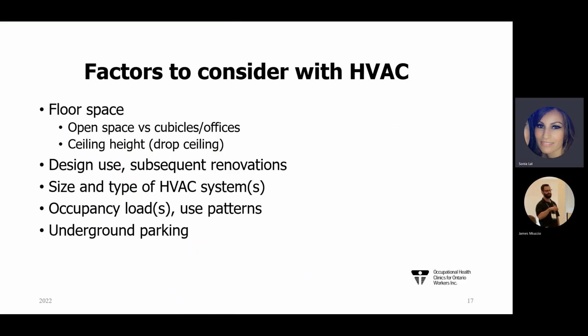Other factors to consider, along with the ones discussed, is the floor space itself. Was it meant to be an open workspace, or was it meant to allow for cubicles? When you install cubicles and obstructions in different areas, you're also affecting how air is distributed to those areas. So those two systems have to talk to one another. If you make changes like that, the air supply to that area has to be able to handle obstructions such as cubicle partitions or bordering panels, etc.